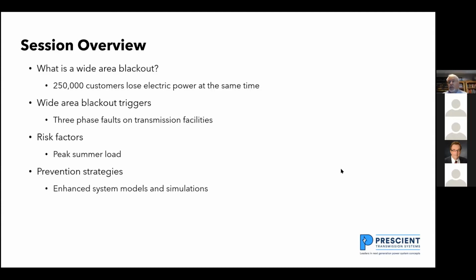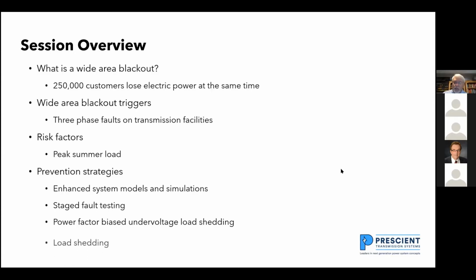The prevention strategies we're thinking about are enhanced system models and enhanced simulations. Staged fault testing. We'd like to see staged fault testing routinely conducted by electric utilities. We're also thinking of adding some new relaying schemes, power factor biased undervoltage load shedding. We're also thinking about traditional load shedding, where if facilities are overloaded, we automatically shed load. And we're thinking about rapid voltage recovery. When a fault occurs today, it takes 100 milliseconds more or less to clear the fault, and you've got a voltage dip for 100 milliseconds. We'd like to see the voltage dip reduced to possibly 8 milliseconds.